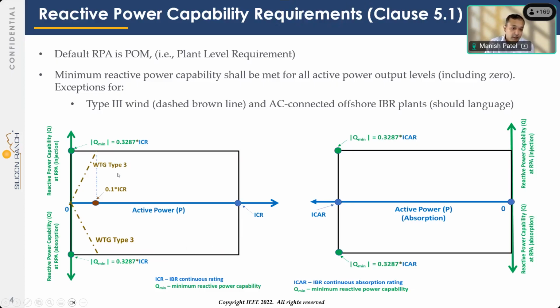Now, in case of type 3 wind turbine generators, we recognize there is a limitation. So when the active power output falls below 10%, the reactive power capability is reduced by this slope line. But in simple words, the plant is required to provide 33% of the ICR otherwise for the whole range of active power output from the plant.